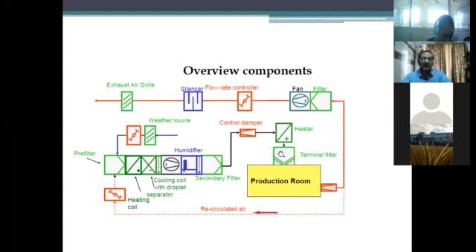Depending on the type of environment in the country, the components of this AHU will change. Air is coming from the top, so the terminal HEPA filter is there, giving you nice sterile filtered air. As you know, the HEPA filter has an efficiency of 99.97% to remove particles of 0.3 micron and larger, so you get sterile air into the room.